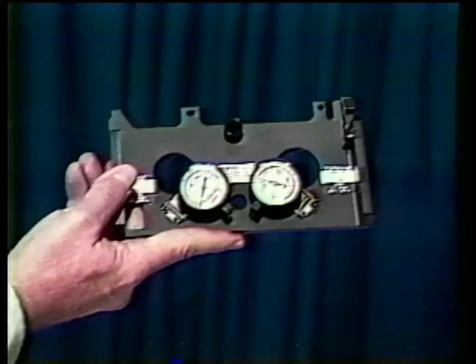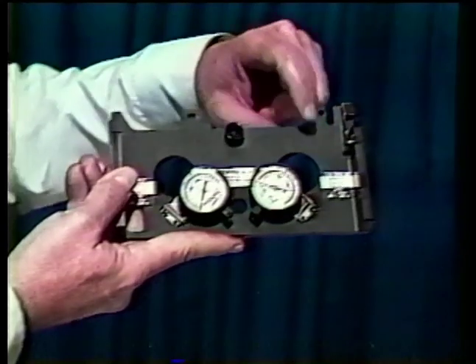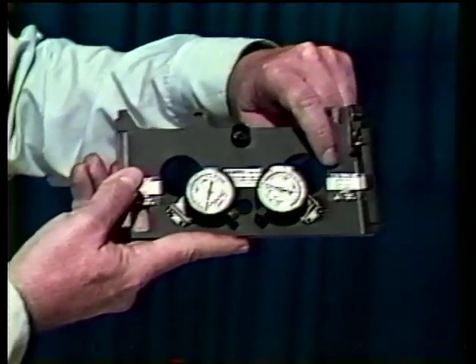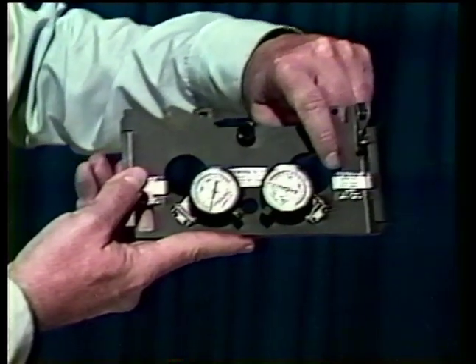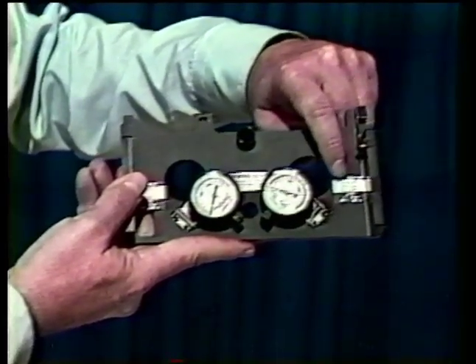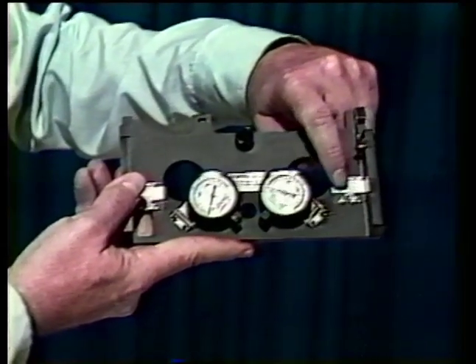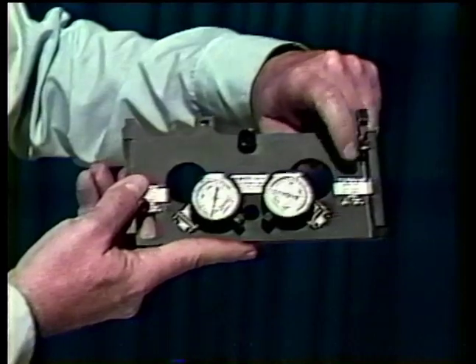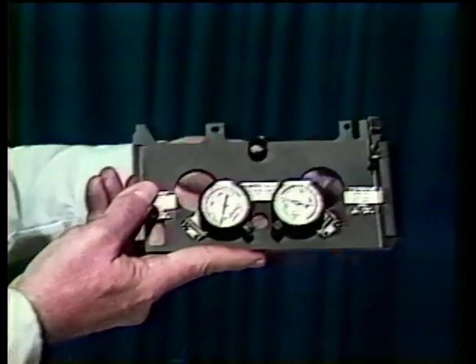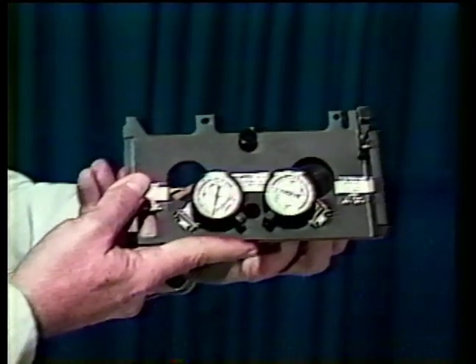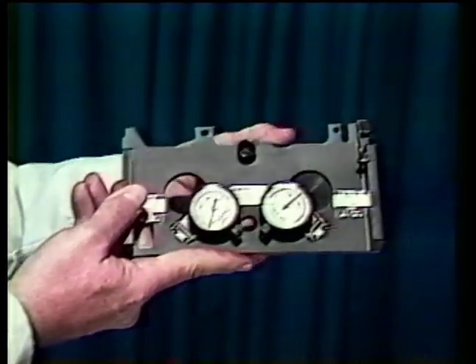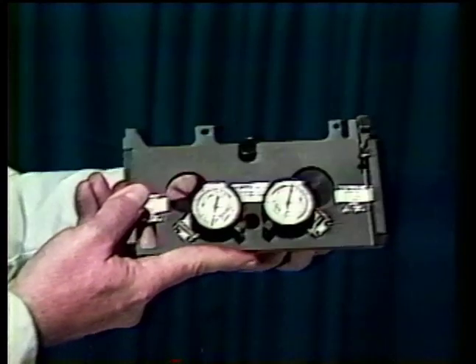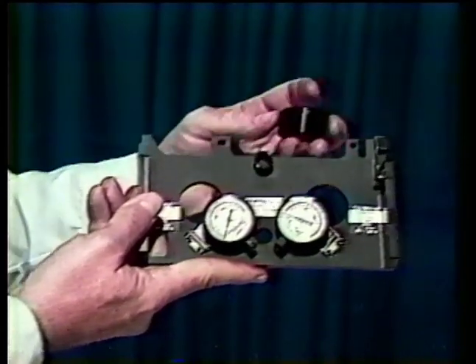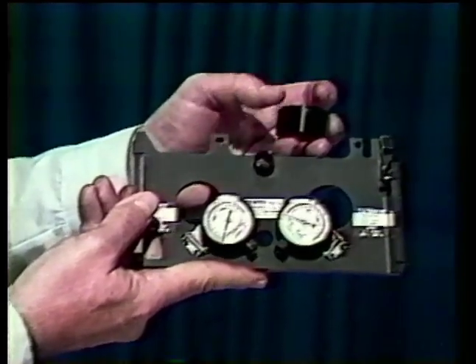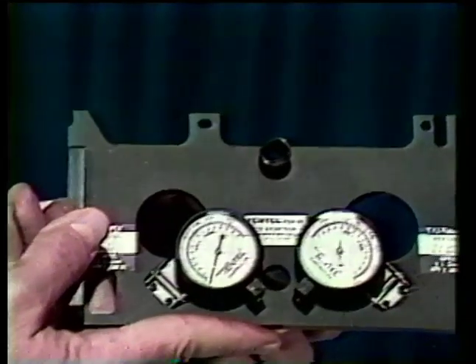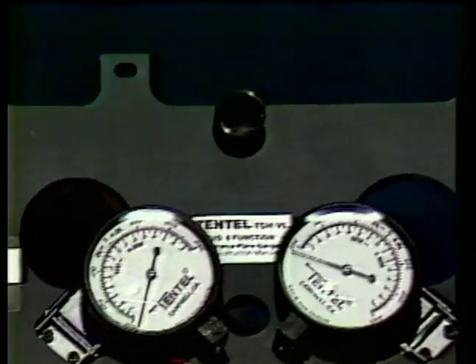It's worth pointing out two additional features of Tentel equipment. Oftentimes we'll try to put the reading right on the gauge itself. This is to aid you. That shows the reading is 0 plus or minus 0.2 millimeters, like we just mentioned, or it shows a specification of 2 plus or minus 0.2 millimeters. So that's on both the take-up and the supply on this gauge. We also supply a master. By inserting the master in the plate, we're able to show that, in this case, of course, it should go to 0, because the master has a 2 millimeter step in the top surface. This 2 millimeter causes the 2 millimeter displacement on the indicator to show up directly.